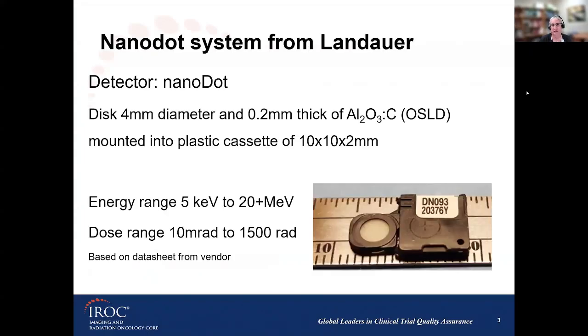So when we talk about the nanoDot system, I would like to make a distinction between two parts of that. The first one is the nanoDot as a detector. This detector has a shape of a 4 millimeters diameter disc, 0.2 millimeters in thickness. The material that is the OSL material is aluminum oxide, and the whole detector is mounted in a plastic cassette of 10 by 10 by 2 millimeters. So it's very suitable regarding dimensions for in vivo dosimetry. And in our case, because it can store the dose without many complications, it has been very useful for external audit. Based on the datasheet from the vendor, you can see here the range in energy as well as the range in dose. Our experience has been using photons, electrons, HDR, and we also have a fully commissioned but never implemented proton system.